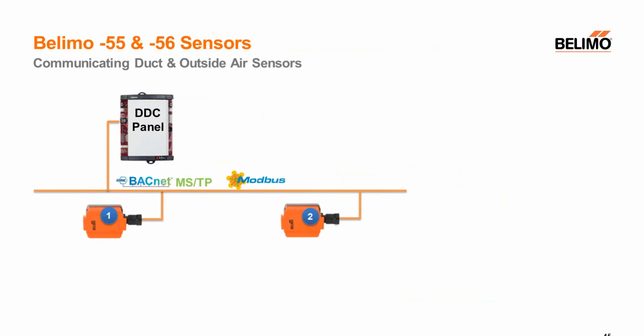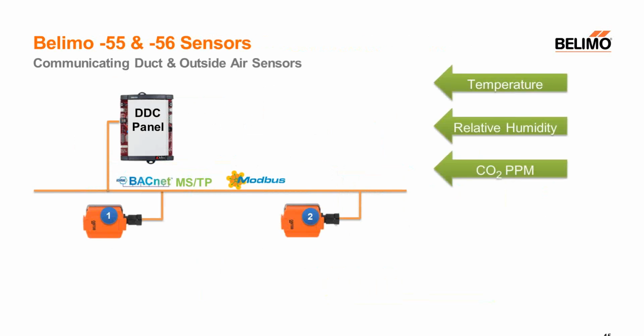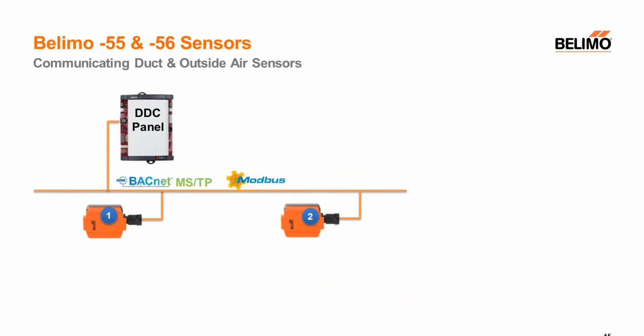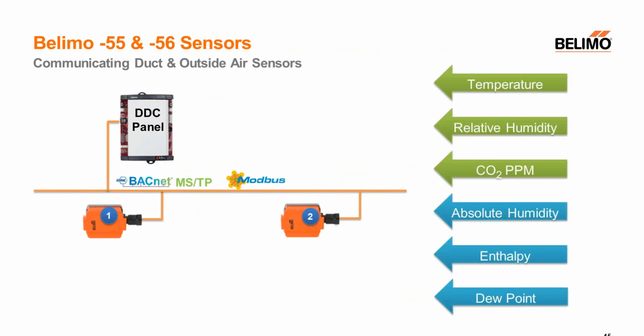With the sensors, they are one or the other. Dash 55 is BACnet and dash 56 is Modbus, and then you use dip switches to actually configure the addressing and speeds and things like that. These are a unique product in that not only can you get a sensor that has temperature, relative humidity, CO2 in the same package, and then get all that information over this 2-wire bus, BACnet or Modbus, you can also get calculated values out of these sensors. So they'll calculate for you absolute humidity, enthalpy, and dew point based upon the temperature and relative humidity. So you get all 6 of those properties all over that 2-wire bus.